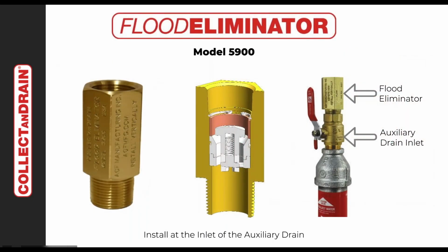The most recent addition to the collect and drain line, which would have been perfect had it been available for this in Texas, but it wasn't, is a product we just introduced called the Model 5900 Flood Eliminator. How this unit works is it is installed above each and every one of your low point drains. If it senses a drop in the pressure because you've had a freeze and a break, or you've had some issue going on at that low point drain, so if there's a drop in pressure below the unit and an increase in the velocity of water coming into the unit, it closes off at the top valve. It still allows a small amount of water, approximately 8 ounces a minute, to drip out of the unit so that you know it needs to be fixed downstream of it.